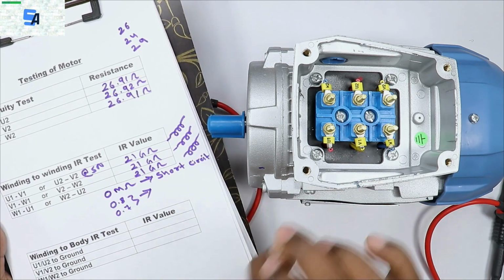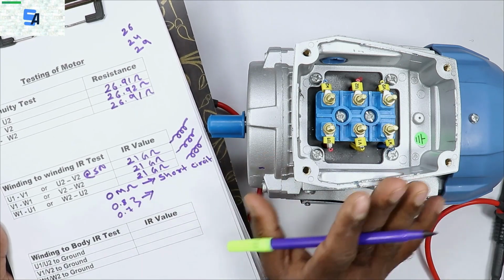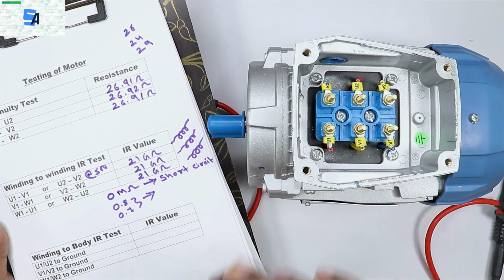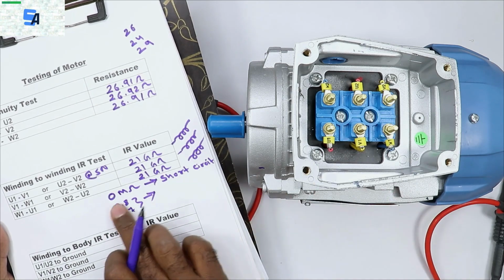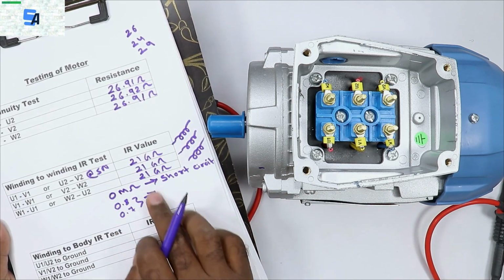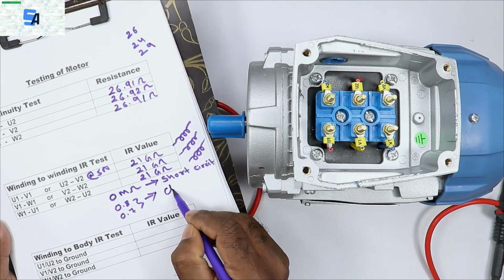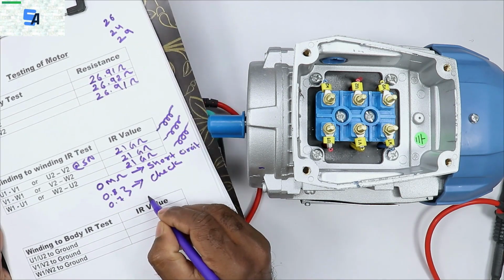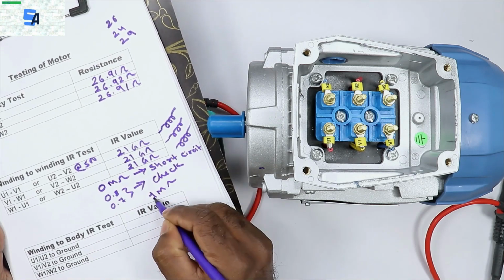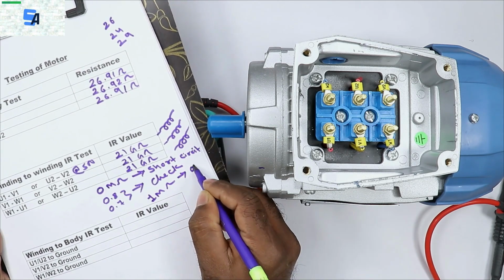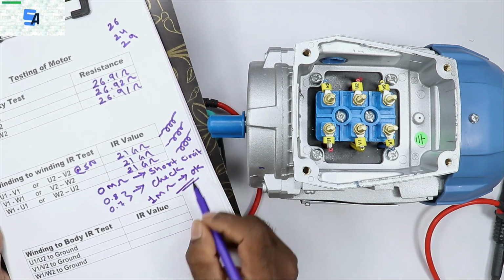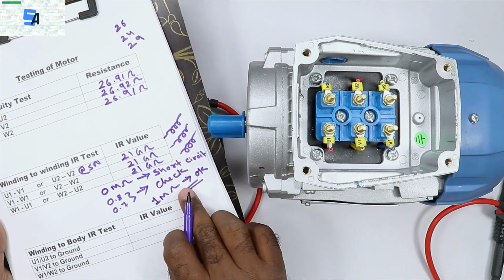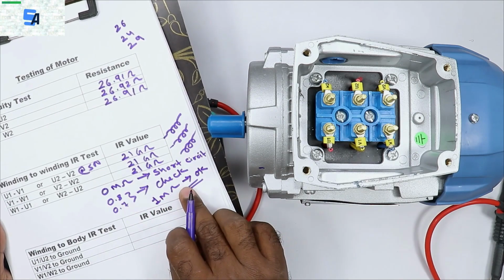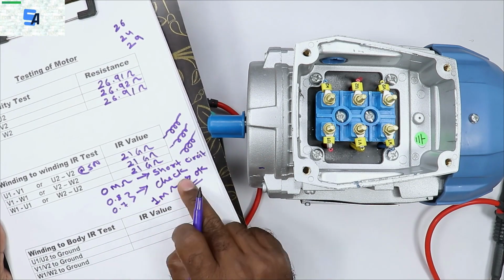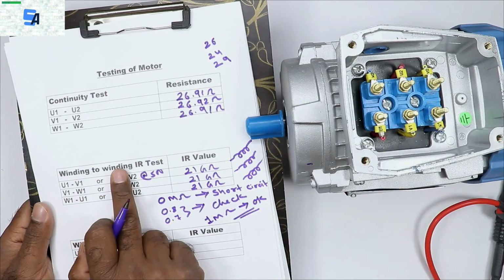The motor will be checked for things like dust or water inside. If there is dust or water inside the motor, the IR value of the motor will also decrease. So when the IR value is very low like this, the motor needs to be checked. And if the IR value of your motor is more than 1 mega ohm, then the motor is fine. This means the IR value of a motor must be at least 1 mega ohm. If it is less than this, the motor needs to be checked. If the value is more than this, there is no problem. So between two windings, you understood how to do the IR test.